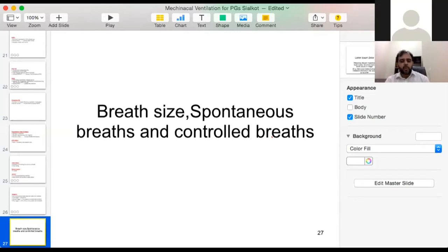These breaths will not be supported unless you add support for them. We will be discussing in the modes how to add support for spontaneous breaths. So for 30 breaths, these are calculated breaths as per the instructions given by the person while setting the parameters like PIP, PEEP, inspiratory time, expiratory time. You have given instruction for 30 breaths, but you have not given instruction for the rest of the 30 breaths. So the rest of the spontaneous breaths will be as per the patient's desire, and the other 30 breaths will be according to the preset parameters. So there will be a difference in these breaths.